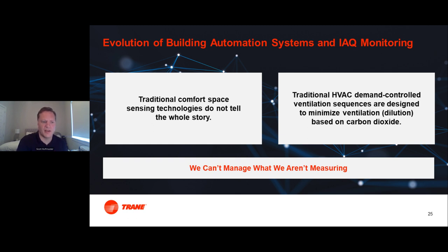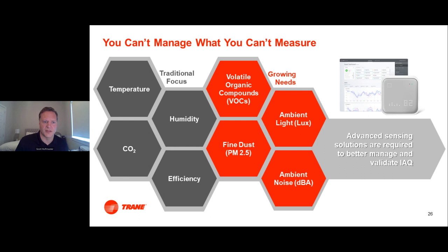With the onset of the pandemic, we are learning what we've already known: there are other things that we may want to consider when we're looking at the indoor air quality of a building versus those traditional focuses. So as we move away from temperature, humidity, CO2, and efficiency, what other things might we consider? Those growing needs would be things like VOC concentration in a space that can lead to odors or other challenges. Fine particulates, which could be called PM1, PM2.5, PM10. One that becomes more common in some of the commercially available sensors is PM2.5.